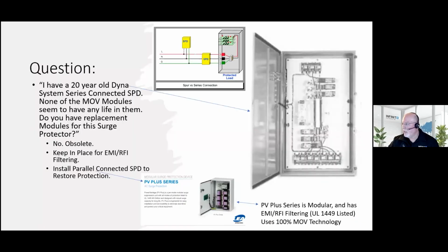And then the next question, and this is very commonly asked, is I've got this old LEA product that is a series connected surge arrestor, and the MOV modules that are in there are shot. Do you still support that? And the answer is no. So we got out of selling series connected surge arrestors. However, what I tell folks is that this filter network is indestructible. The MOV protection is not there anymore, so you're not being protected from surge if you have this device, but you've got one of the best EMI RFI filters ever. So what I recommend you do is keep this in place, because to remove it, you'll have to secure power to the whole building. And instead, install a parallel connected surge arrestor like this one, which has filtering built into it. This particular one has MOV modules and filter modules separately.